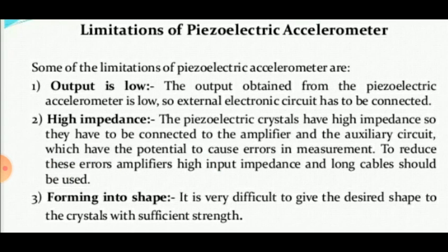Then the disadvantages of piezoelectric accelerometers. First, the output is low. The output obtained from the piezoelectric accelerometer is low, so an external electronic circuit has to be connected. Second is high impedance. The piezoelectric crystals have high impedance, so they have to be connected to an amplifier and auxiliary circuit, which have the potential to cause errors in measurement.